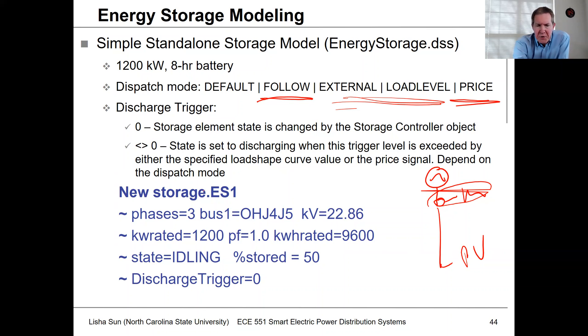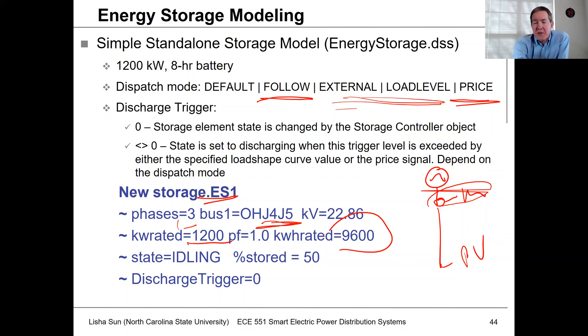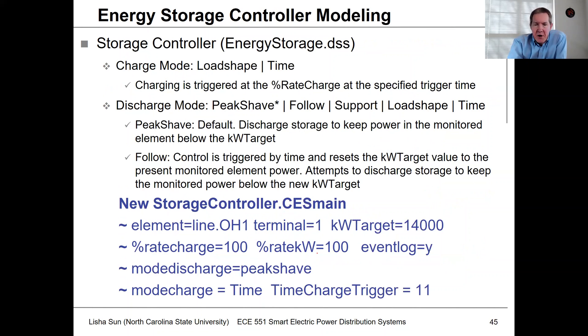What we're doing in this case is defining a new storage device. It's three-phase, installed at a specific location, rated in kilowatts. The energy capacity is 9,600 kilowatt-hours. At 1,200 kW, that would be 9,600 divided by 1,200 — an eight-hour battery. We also set the initial state of charge.